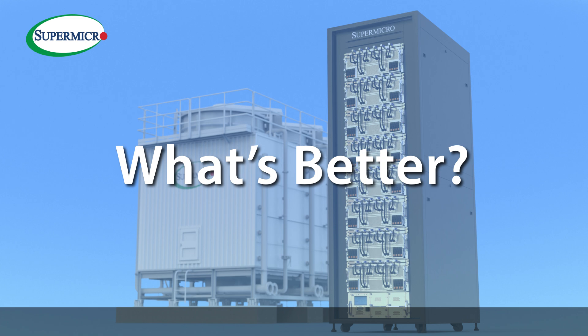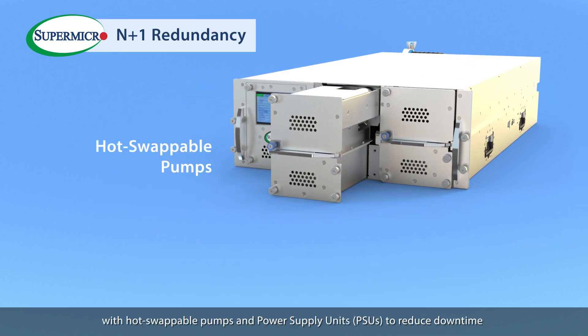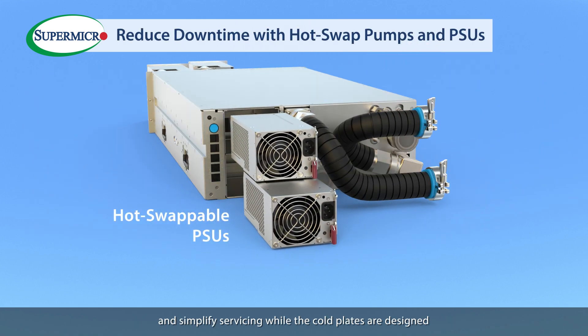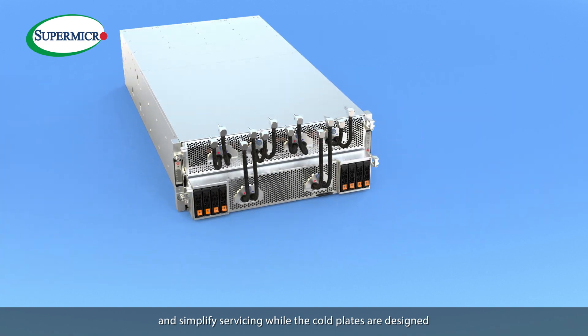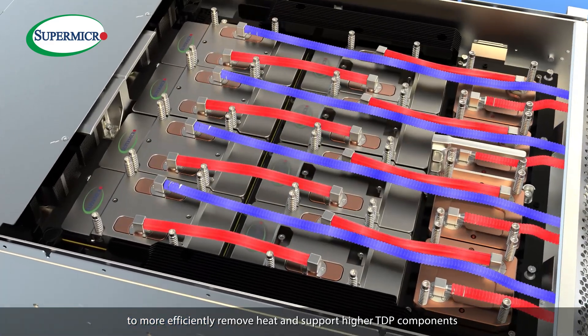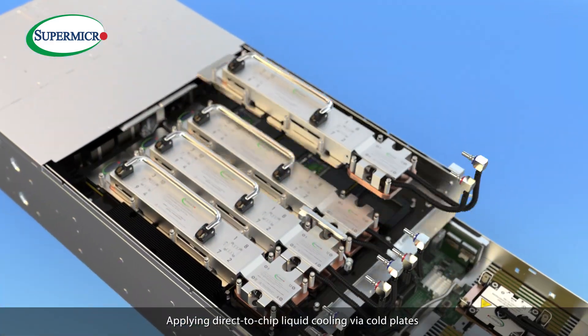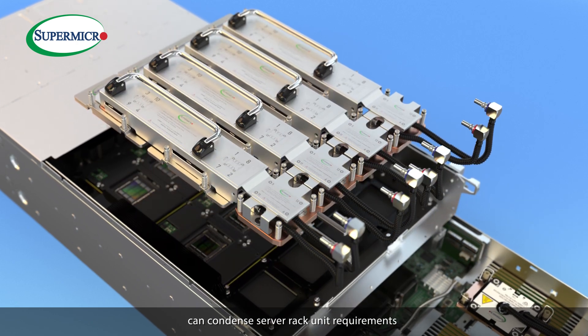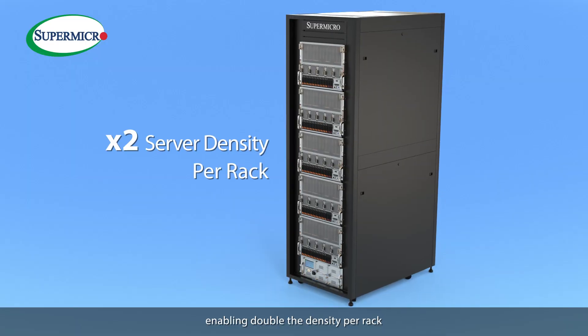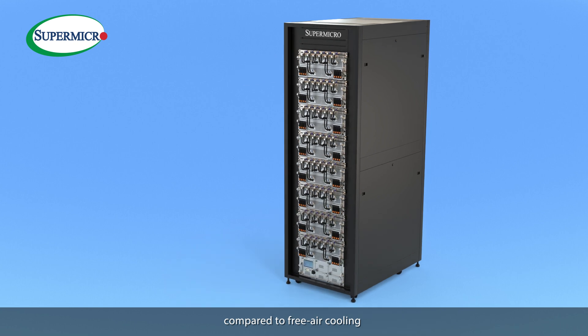What's better? The 4U CDU features N+1 redundancy with hot-swappable pumps and power supply units to reduce downtime and simplify servicing, while the cold plates are designed for lower than industry-standard thermal resistance to more efficiently remove heat and support higher TDP components. Applying direct-to-chip liquid cooling via cold plates condenses server rack unit requirements, enabling double the density per rack and more compute for the same power budget compared to free-air cooling.